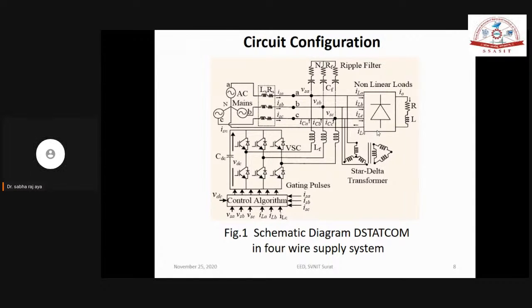That is the meaning. Okay, then what is the frequency of the neutral current? 150 hertz, third harmonic only. And that is going to circulate inside the delta connected winding. It will circulate only; it will not go anywhere. So that is going to circulate and finally make losses only. Okay.